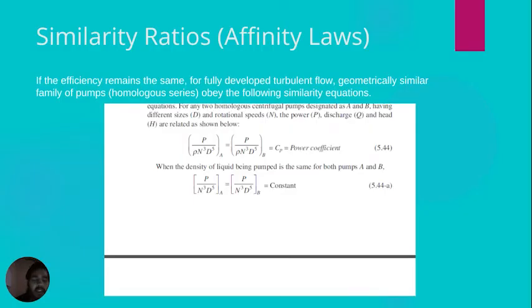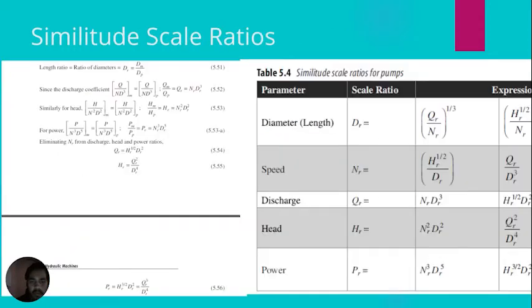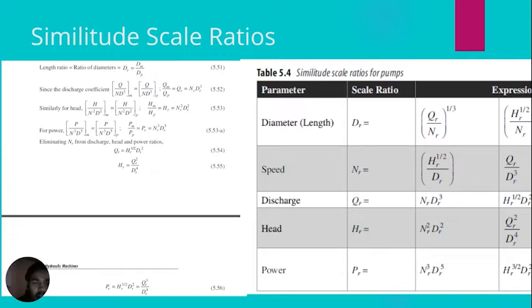We define a new feature known as similarity scale ratios. Taking a ratio r of different entities: the length ratio is the ratio of diameter D of model upon D of prototype. For the discharge or flow coefficient, Qr equals Nr·Dr³. For the head coefficient, Hr equals Nr²·Dr². For the power coefficient, Pr equals Nr³·Dr⁵.